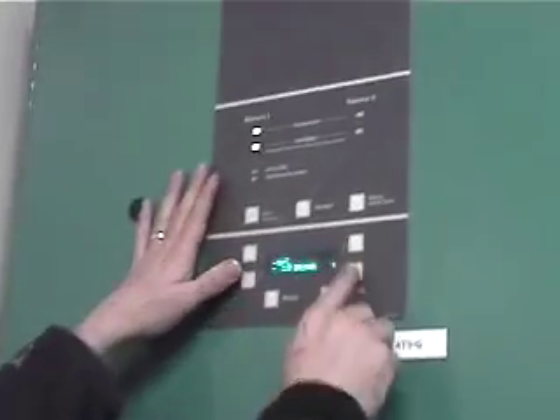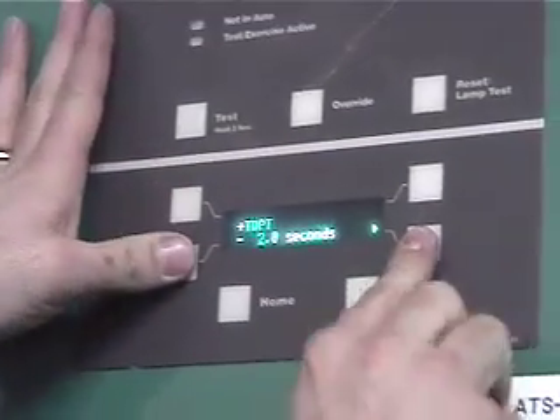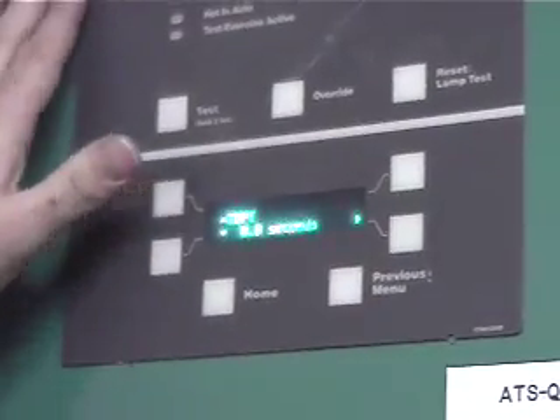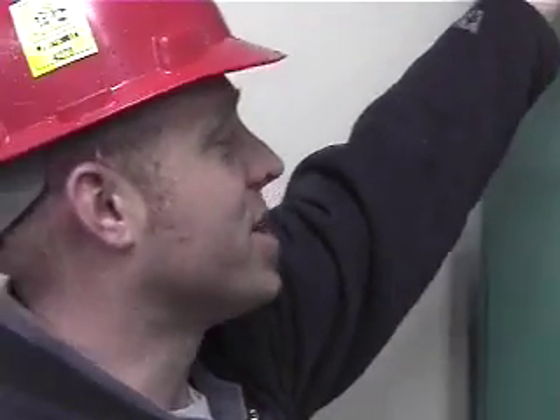What that means is when it transfers with a test, or when it returns from generator back to utility, there's no bump. There's no interruption of power. The loads will not drop out. Obviously, if the power goes out, it's going to, because you can't foresee a power outage. But during a test, it's going to transfer back with no interruption of power. So that's why I had this set for 0 seconds. I'm going to change that back down because I don't want it to stop in neutral, because it's a closed transition switch. Most transfer switches are an open transition, where you get the bump. Basically, you're going to see a bump every time it transfers. This one is not.